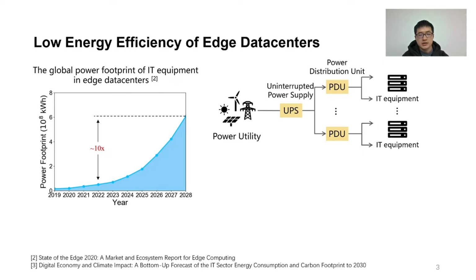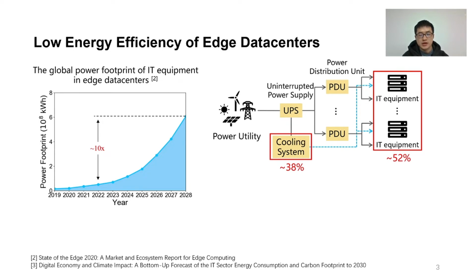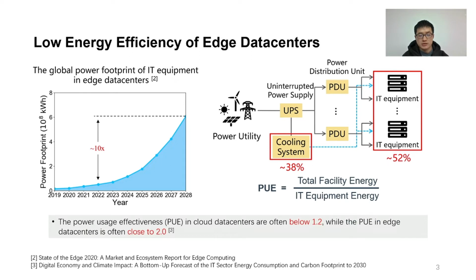Besides the IT equipment, there are other kinds of facilities in a data center, such as the power system like UPS and the cooling system. The IT equipment usually contributes over half of the total facility energy, and the cooling system dominates the rest. A useful metric, power usage effectiveness, or PUE, is usually used to indicate the energy efficiency of data centers. It's calculated by the total facility energy dividing the IT equipment energy. Although the PUE of cloud data centers can reach near 1, the PUE of edge data centers is as high as around 2, showing the low energy efficiency of current edge data centers.